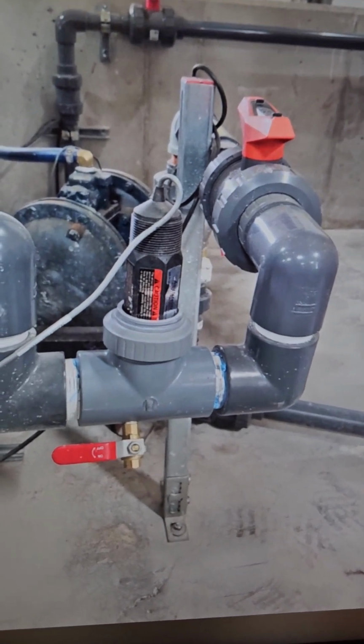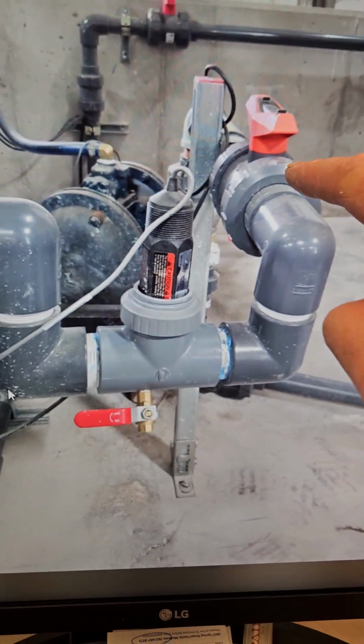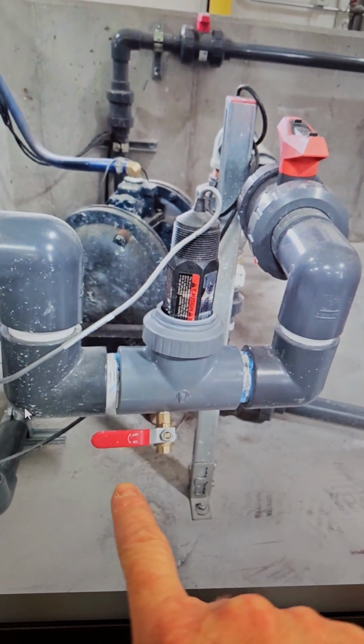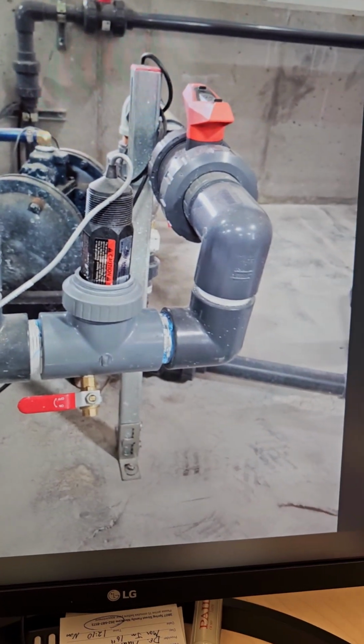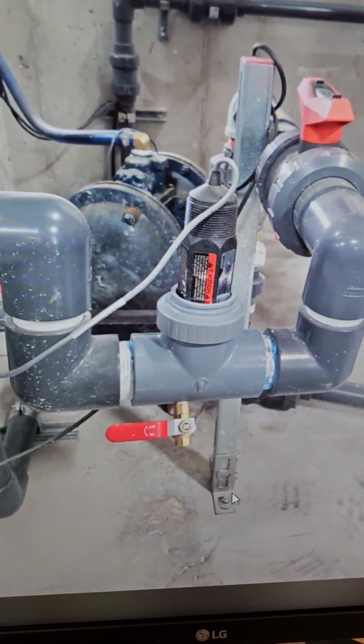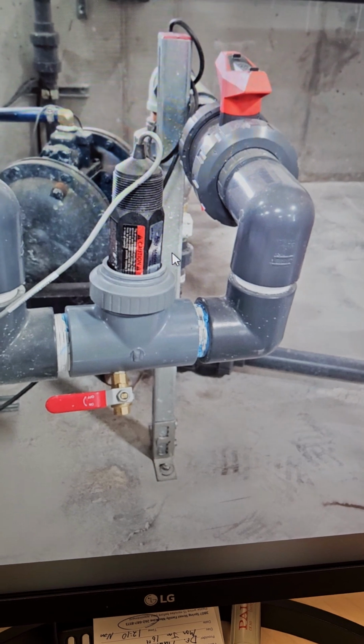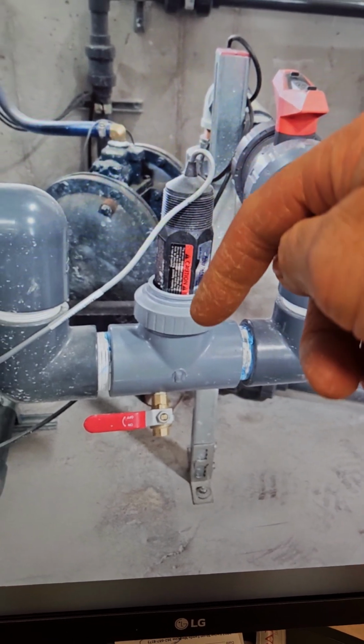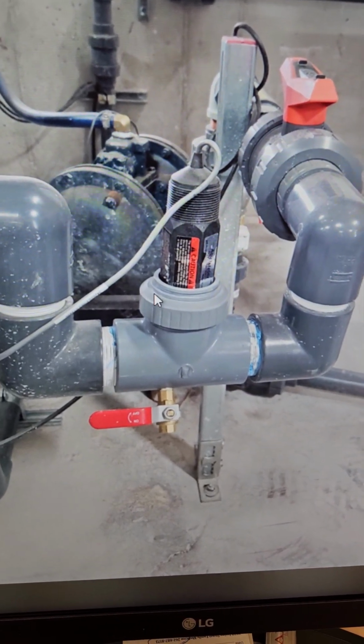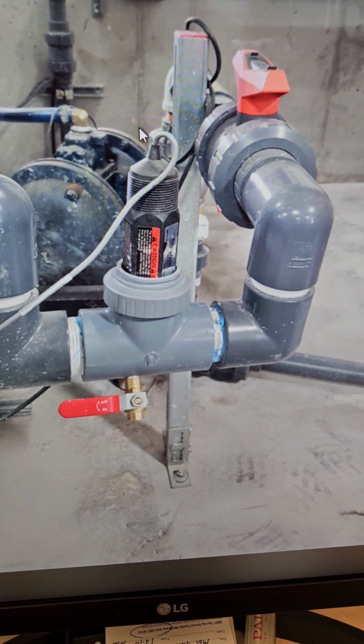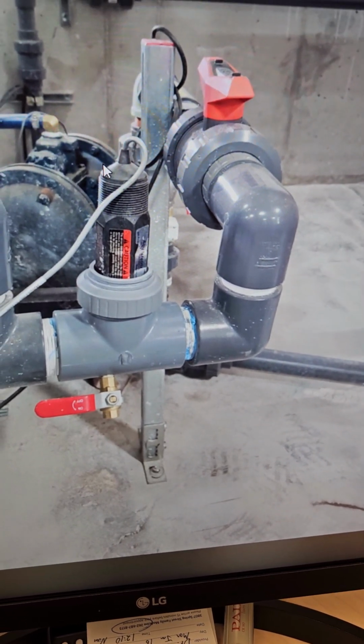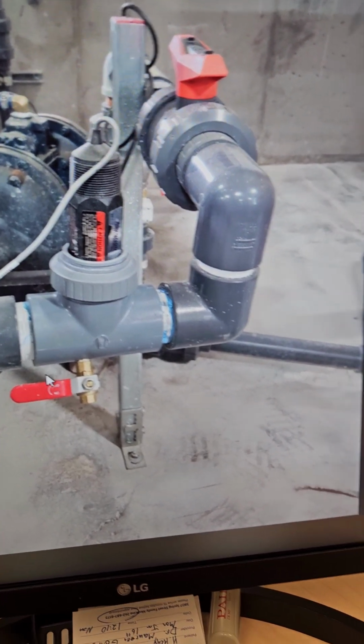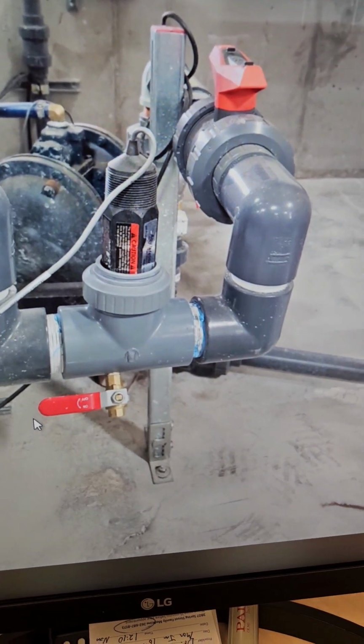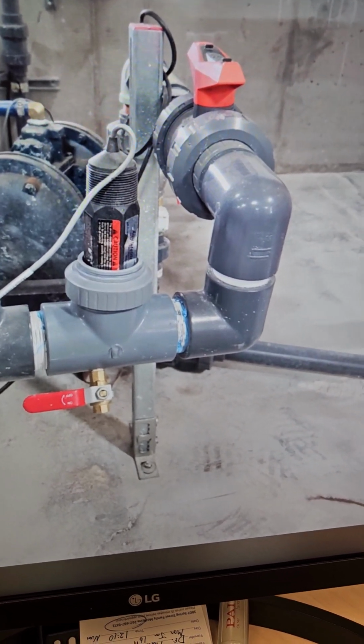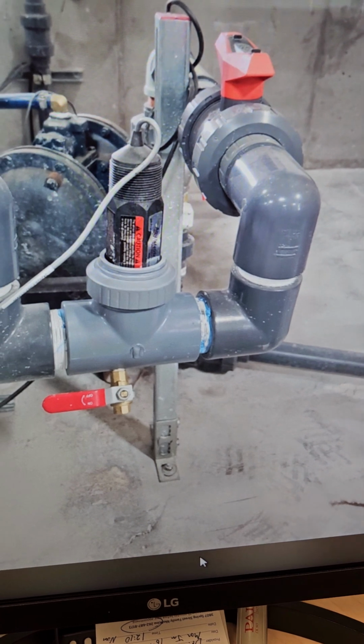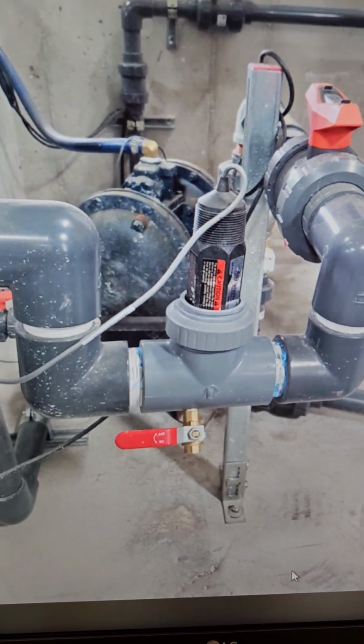Here's a trap. What I add is, so when they isolate it to pull it out, I just open up a drain valve and put a bucket or something underneath it. Water can drain out, air can get in, and then it becomes very easy to open up the union nut and take it out. So then air is able to come in as it comes out. Just don't forget to shut that before you put it back in operation, or you have water squirting out of there. Sometimes a pail underneath there is all you need to fix that.